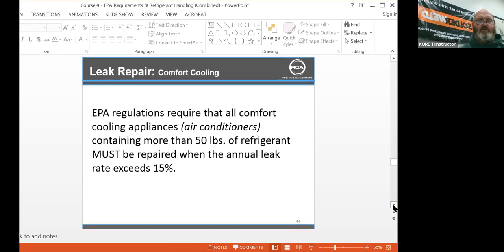It's pretty standard. EPA regulations require that all comfort cooling appliances or air conditioning containing more than 50 pounds of refrigerant must be repaired when the annual leak rate exceeds 15%. Again, that would be in our supermarket systems where maybe we've got an air handler tied to a rack, or a large buildup on the roof on older market systems where you've got some 30, 40, 50 or 60-ton condensing units tied to an air handler. You could have over 50 pounds of refrigerant.